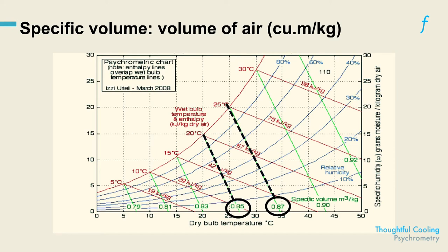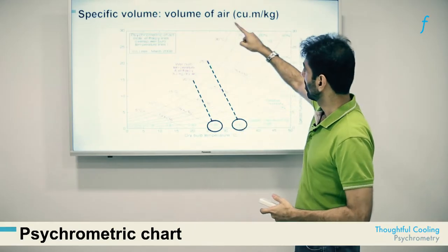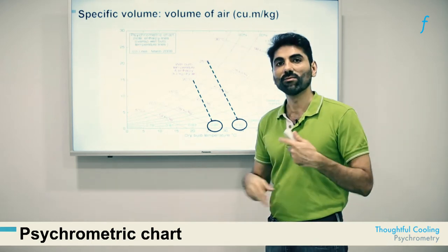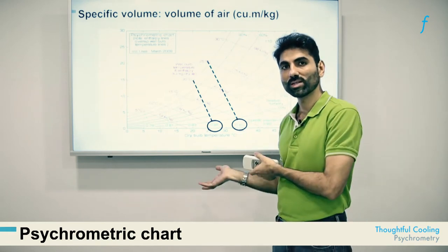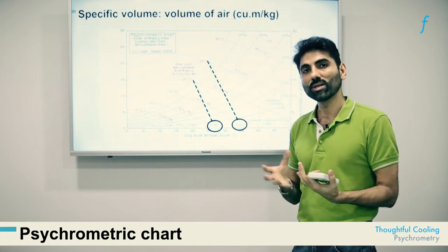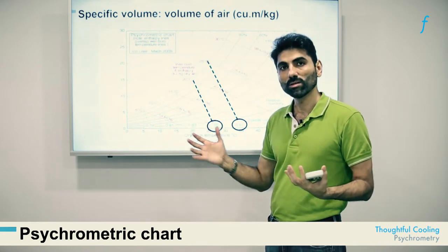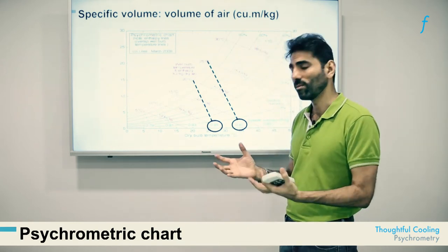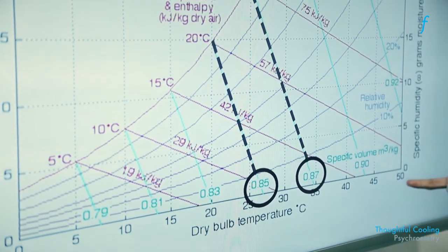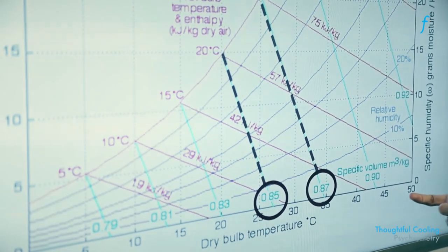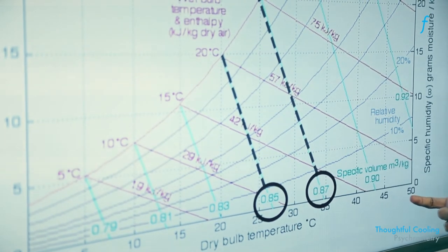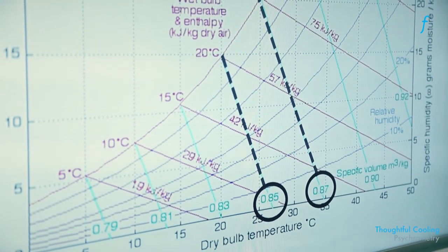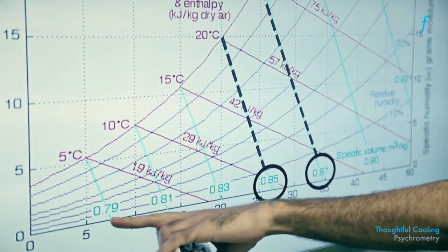The sixth layer is called specific volume, which is nothing but the inverse of density. Since density is inversely proportional to temperature — warmer things are lighter — as you go to the right the density of air reduces, which means specific volume increases. It increases from 0.79 cubic metres per kg up to 0.9 cubic metres per kg, meaning one kg of air occupies 0.9 cubic metres when warm versus only 0.79 cubic metres when cold and denser.